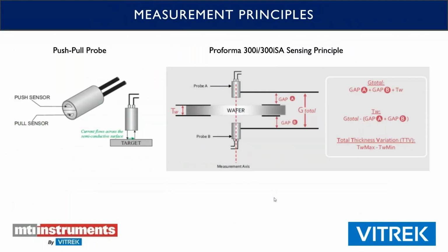So the measurement principles, with these tools, it uses opposing probes. Our push-pull probe is actually two sensors built into one probe body. As you can see on the left here, there's a signal that comes out of the push side of the probe, and it goes across the target to the pull sensor, which is run at the same frequency, but there's a 180-degree phase shift, which basically shoots the target down one side and then sucks it back up the other.